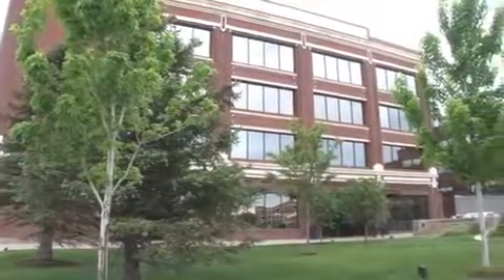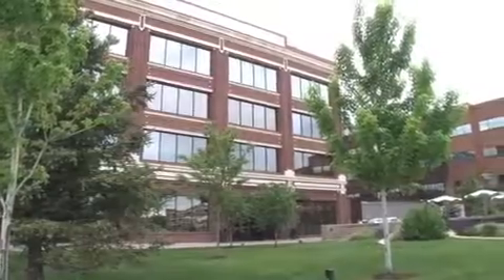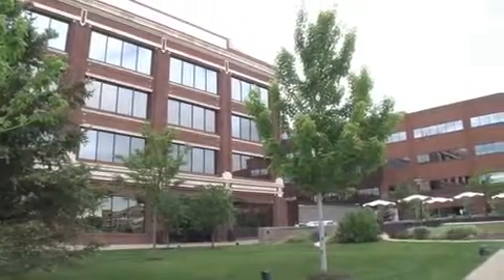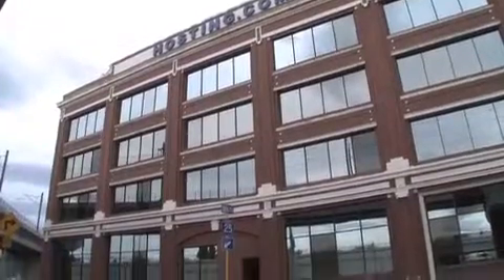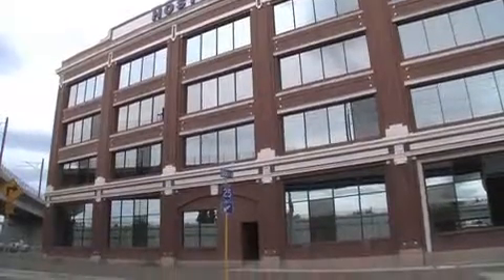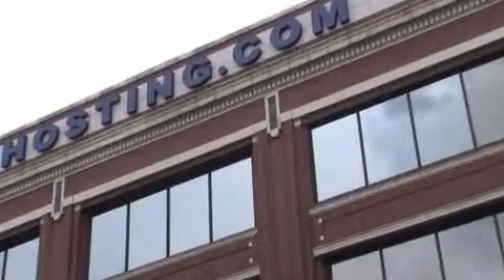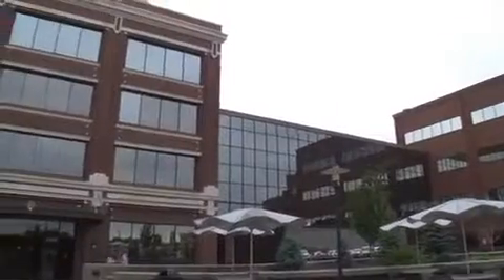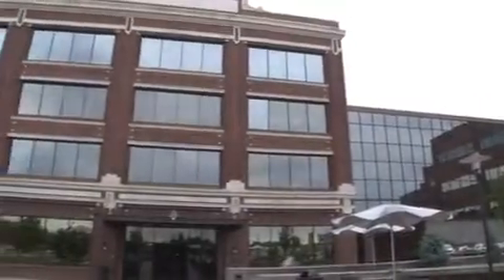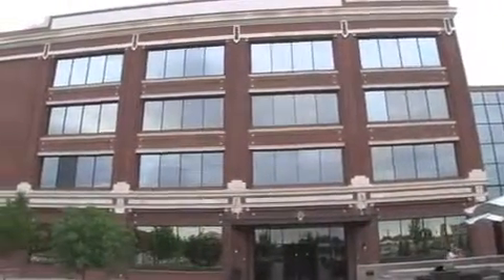The facility itself has a rich history, being originally a Model T manufacturing plant. And since it was a Model T manufacturing plant, it brings a lot of good characteristics. First and foremost is the amount of power that comes into the facility, which is probably the most important criteria whenever building and selecting a location from a data center perspective. It has around 14 megawatts of power coming into the building, which makes it one of the highest power density locations in the metropolitan area.